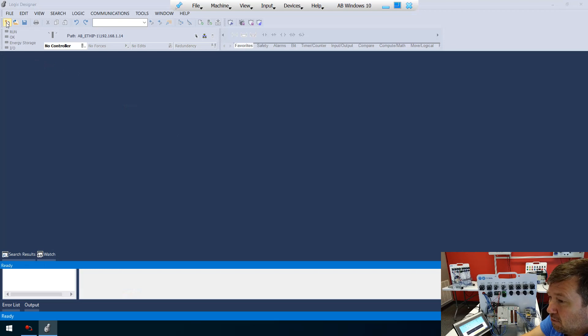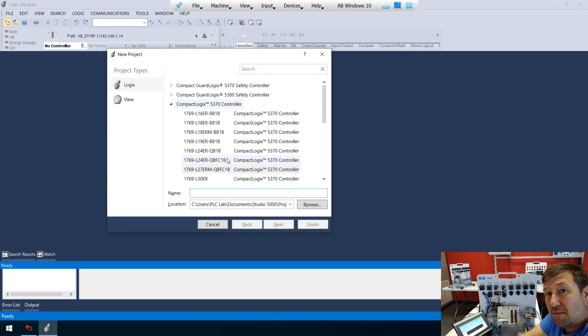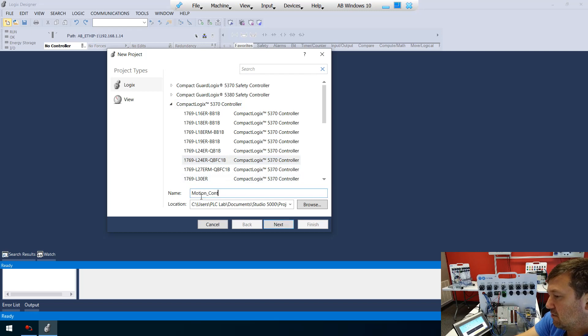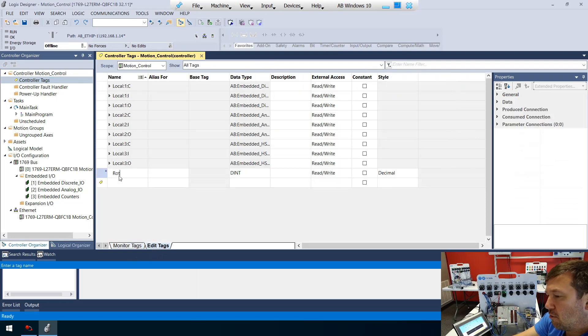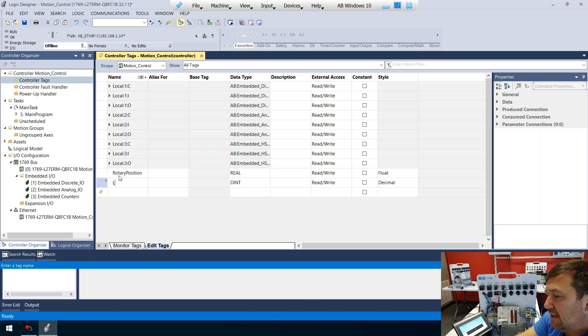We're going to create a new program using a 1769-L24ER-QBFC1B. We'll select it and call this our motion control, then hit next and finish. Then we're going to open up our controller tags and create two tags. Go to the edit tag tab and create rotary position as a real, and linear position also as a real. Those are mainly just to communicate with our HMI — they're not actually required for the high-speed counter setup.